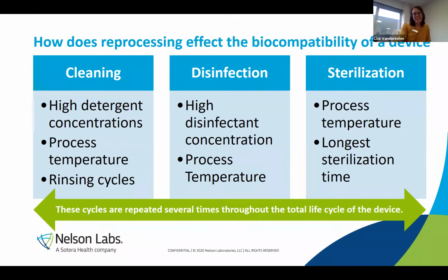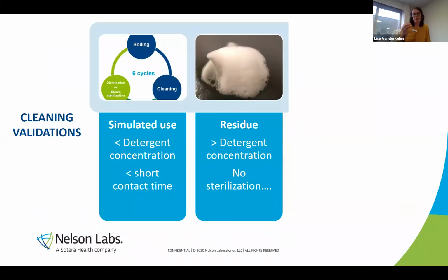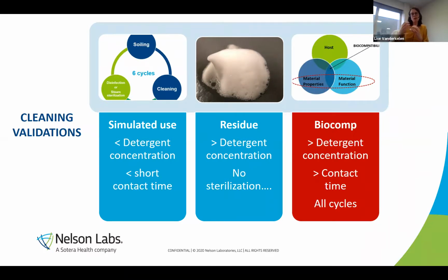So when we look just at cleaning today, in a cleaning validation, during the simulated use, we'll use low detergent concentration and shortest contact time of the detergent with the device. When we look at the residue testing, we will have high detergent concentration and we'll not include the final step. The cytotox test will be done after the cleaning. We'll not do the disinfection or the sterilization. Whereas in the biocompatibility testing, when we look at what challenges the material properties, it is high detergent concentration, long contact time, and it should include all reprocessing cycles. So you see there is a little bit of a gap between the cytotox test and how the sample is prepared for a cleaning validation compared to how somebody from a biocompatibility background will look at it.